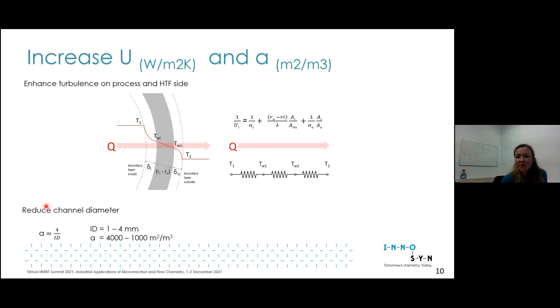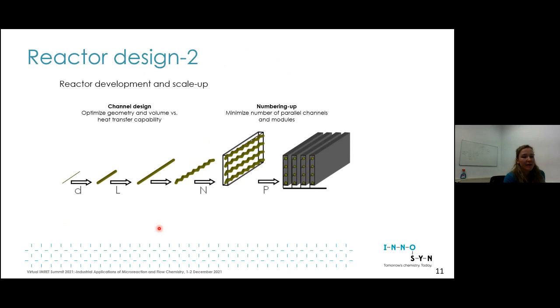You have resistance at the process side, then conduction through the wall to the cooling side. You can maximize heat transfer coefficient by maximizing turbulence on both sides. The conduction is quite high because we mostly use stainless steel reactors and the channel thickness is quite thin. The other parameter is transfer area, simply the surface to volume ratio.